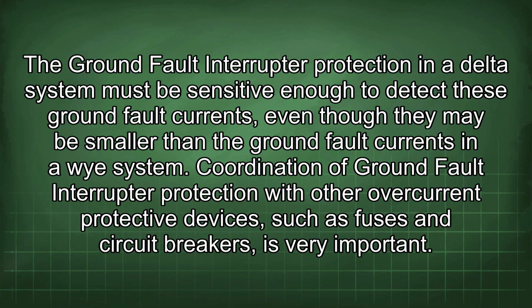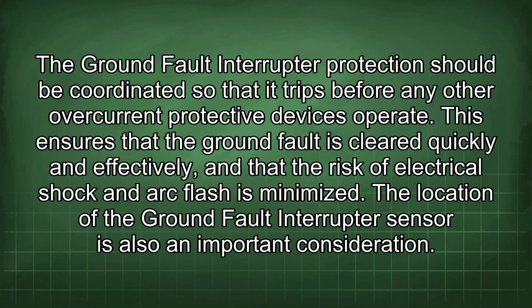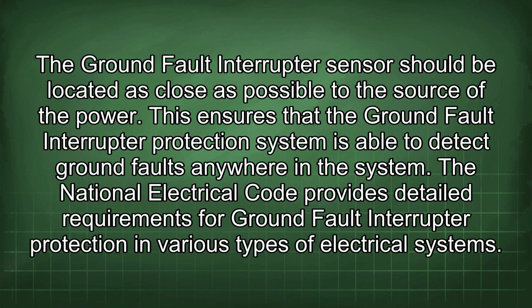Coordination of ground fault interrupter protection with other overcurrent protective devices, such as fuses and circuit breakers, is very important. The ground fault interrupter protection should be coordinated so that it trips before any other overcurrent protective devices operate. This ensures that the ground fault is cleared quickly and effectively, and that the risk of electrical shock and arc flash is minimized. The location of the ground fault interrupter sensor is also an important consideration. The sensor should be located as close as possible to the source of the power. This ensures that the protection system is able to detect ground faults anywhere in the system.